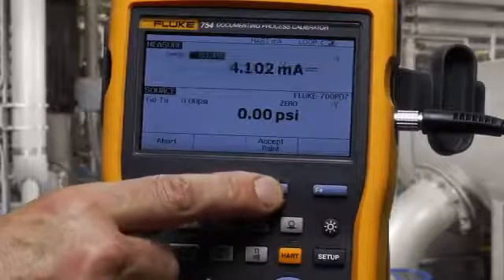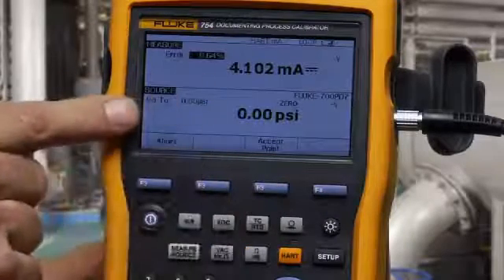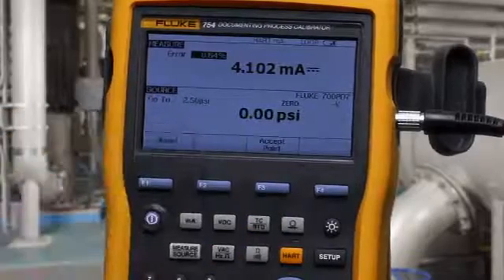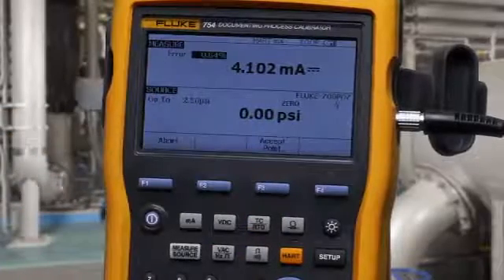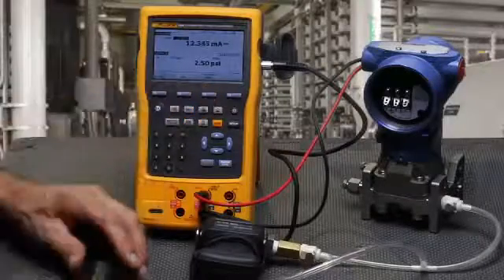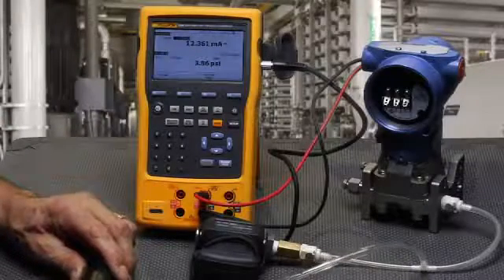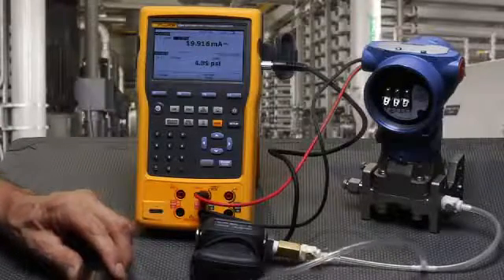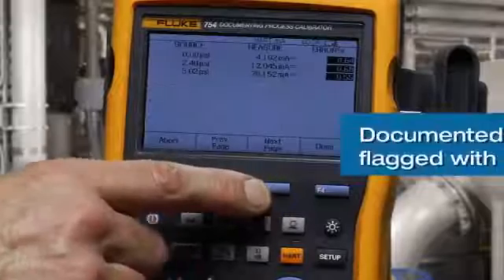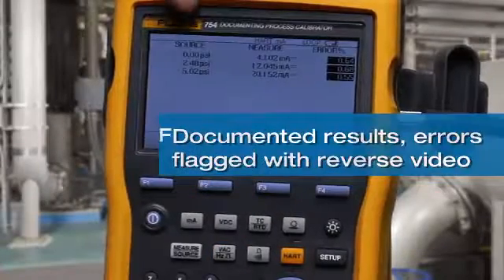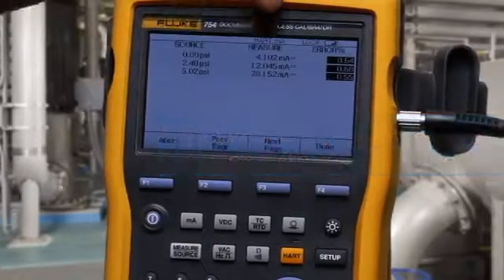Manual test tells us the pressure to apply. Accept. Go to 2.5 PSI. Pump up to 2.5 PSI and accept. And go to 5 PSI and accept. And you have the recorded pressure that's applied, the milliamp that's measured, and the error percent of span.